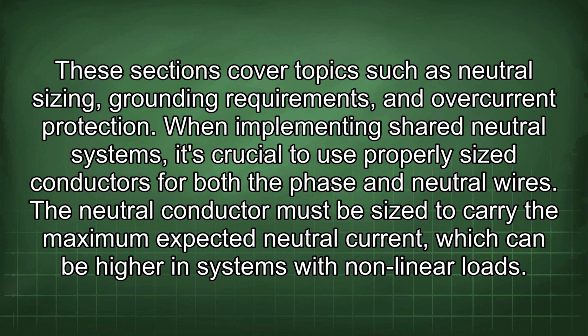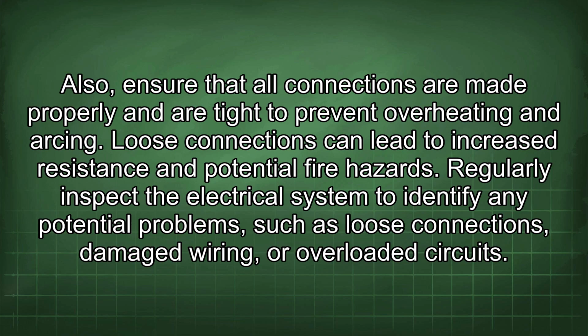When implementing shared neutral systems, it's crucial to use properly sized conductors for both the phase and neutral wires. The neutral conductor must be sized to carry the maximum expected neutral current, which can be higher in systems with non-linear loads. Also, ensure that all connections are made properly and are tight to prevent overheating and arcing. Loose connections can lead to increased resistance and potential fire hazards.